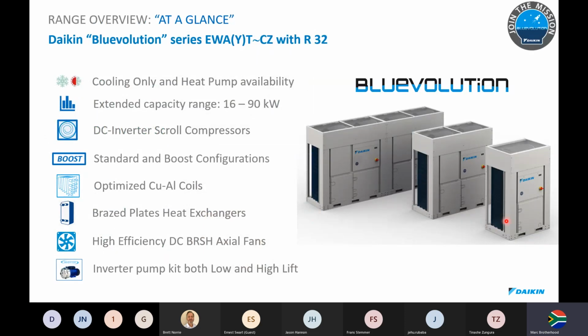This is our new 2021 range that's come through. At a glance, it comes in cooling only as well as heat pump. We've increased the range from 63 kilowatts up to a 90 kilowatt range. These all run on DC inverter scrolls, so this is digitally commutated through our inverter technology. We have the standard as well as boost configurations. What the boost pretty much means is we can overgenerate voltage on the inverter board to run the compressors up to around 130% for quick pull down times. Copper and aluminium coils, braze plate heat exchangers, high efficiency digitally commutated brushless axial fans. So these are pretty much hub motors.